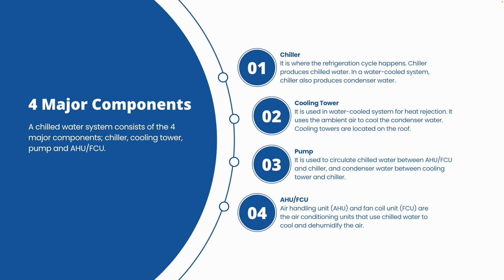Chilled water is low-temperature water, usually around 5 to 7 degrees Celsius. There are many types of chillers, which will be covered in a dedicated chapter. In a water-cooled system, the chiller also produces condenser water for heat rejection. That brings us to the second component — the cooling tower. Condenser water goes to the cooling tower, which uses its fan to bring in ambient air and cool down the condenser water. The cooling tower is the large unit you can see located on the roof.